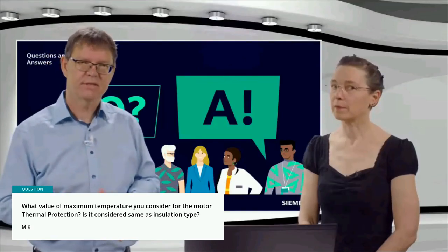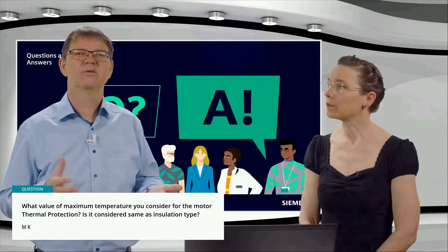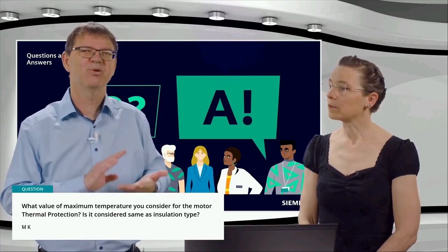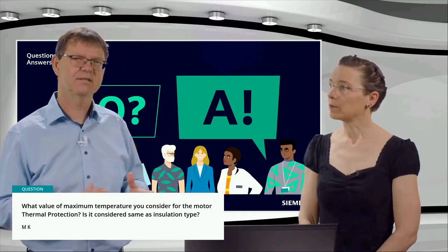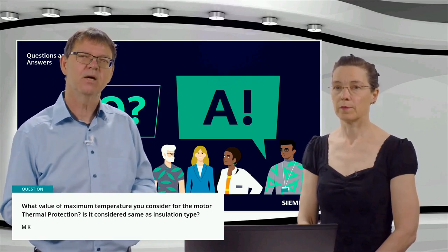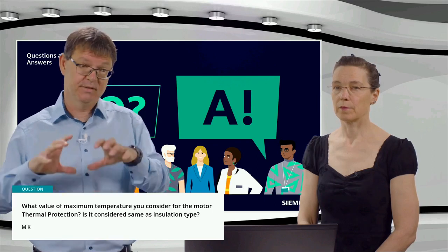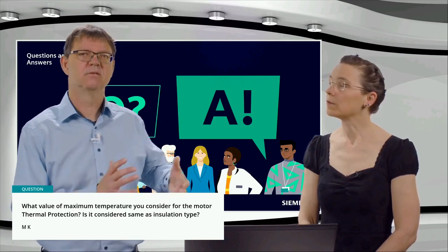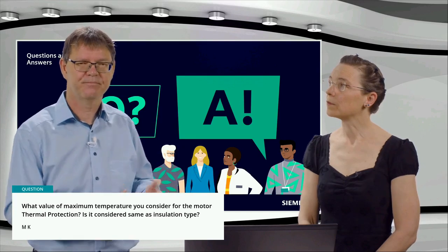Here we don't consider that at all, because we consider just the data we have from the motor manufacturers: the number of starts, the starting time and the starting current. All together with that, we build up our model for the rotor. And again, this rotor temperature model is completely independent of the stator temperature model.